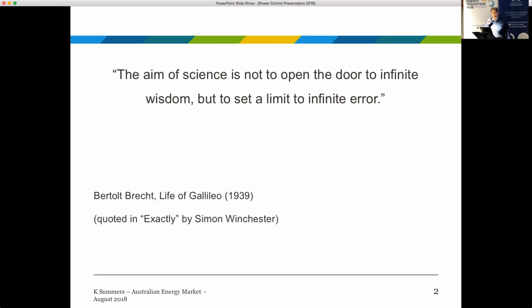If we lose our understanding of what active energy does to the power system, and think we can control energy dispatch in ignorance of frequency control, we've lost the plot. So in 2001, when we set up a frequency control ancillary service market, did we actually understand what that was doing to the control of frequency? Let's examine what the frequency control ancillary service market is and is not, to get a clear understanding of what it's doing to the power system, so we can understand what we want to do when we transition and put new stuff into the power system.